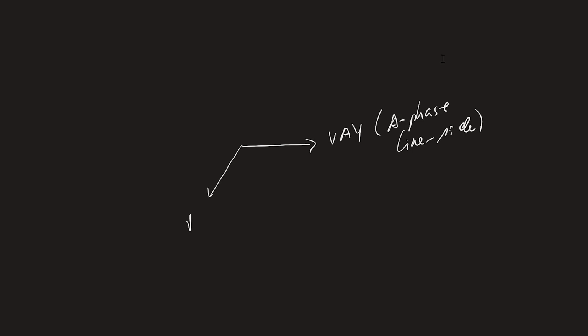And again, this would be wired to VAZ, but it's actually the B phase bus side voltage. And so you need to tell the relay, compensate for this difference because you're not comparing apples to apples. You're comparing A phase from the line side to B phase from the bus side. So you need to shift or compensate for the phase shift of the B phase so that you can compare it to the A phase on the other side. That's what that setting is for, KS1A.